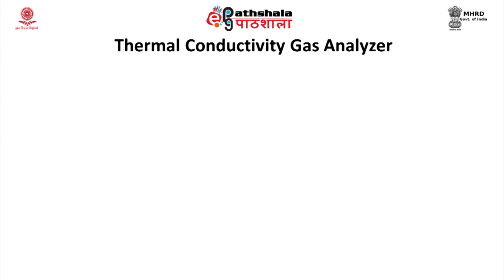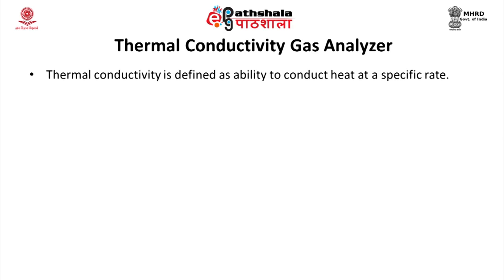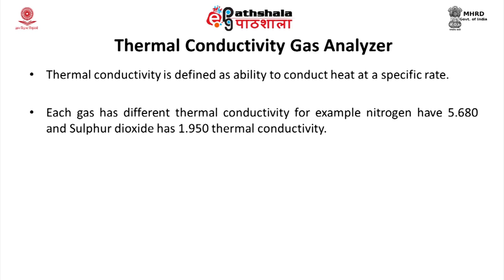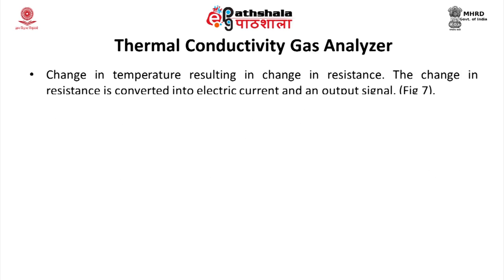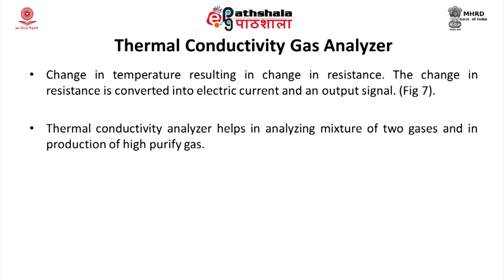Thermal conductivity is defined as the ability to conduct heat at a specific rate. Each gas has a different thermal conductivity — for example, nitrogen has 5.680 and sulfur dioxide has 1.950. The zero and sample gas are passed onto a heated metal filament. The amount of heat carried away by the gas changes the rate of cooling of the filament wire, causing a change in temperature and a resulting change in resistance. This change in resistance is converted into an electrical signal or current as an output signal. Thermal conductivity analyzers help in analyzing mixtures of two gases and in the production of high-purity gases.